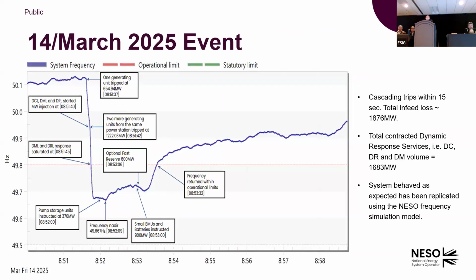I'd like to talk a little bit about one event that happened in the system after the commissioning of the grid forming batteries. We had quite a big generation loss event around March, just after the commissioning, but that's not related. We had 3 generation trips within a very short period of around 15 seconds, and the infeed loss was around 2 gigawatts. For the GB system, just for context, the maximum infeed loss we secure is around 1.8 gigawatts. So in theory, that's over what we normally secure for a security event.